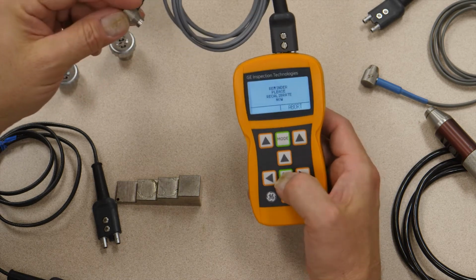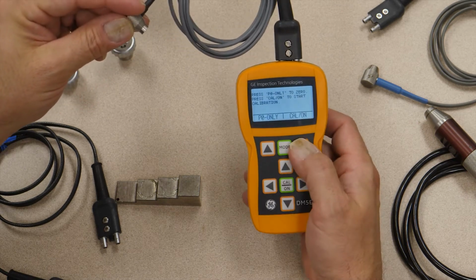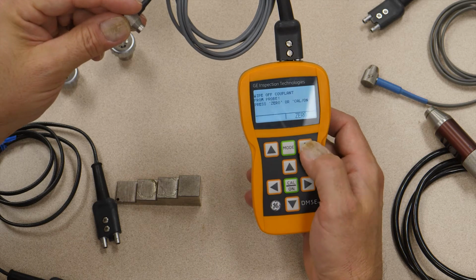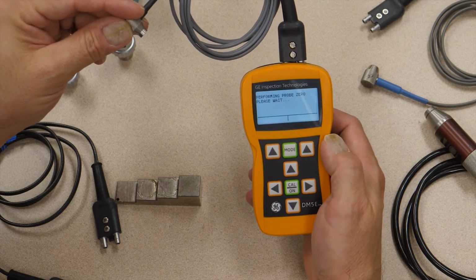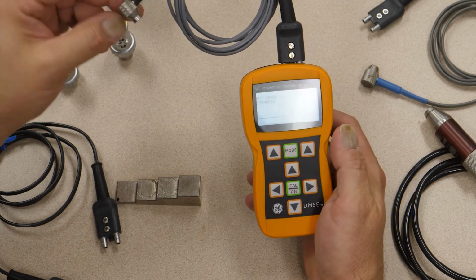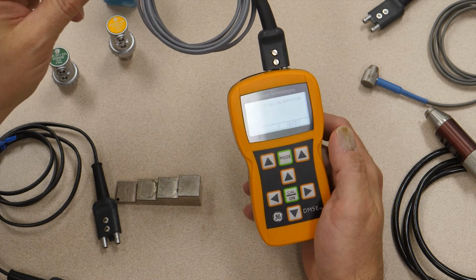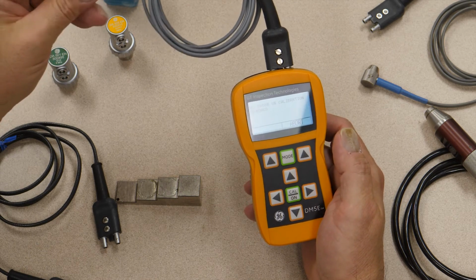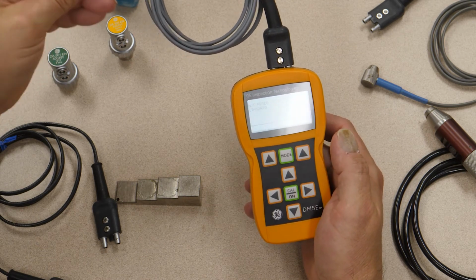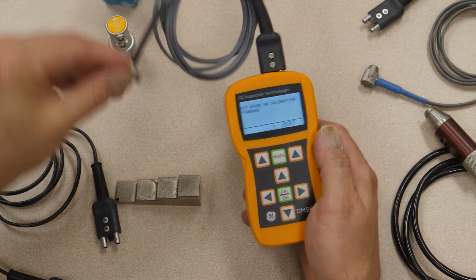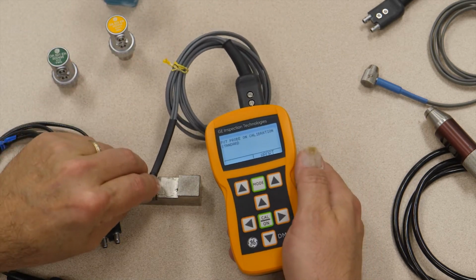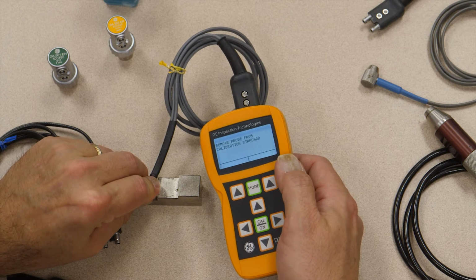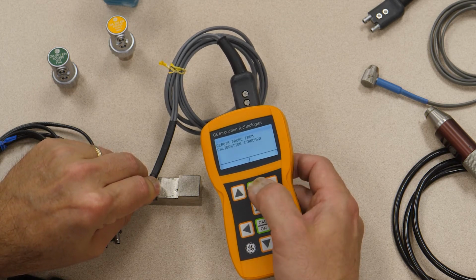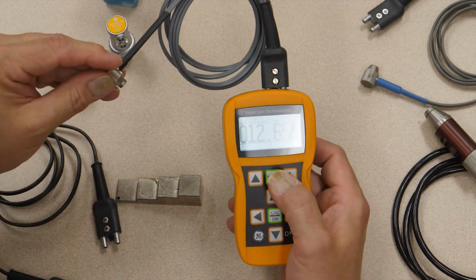We need to run through a calibration. So I say calibrate. I'm going to do a full calibration. I zero the probe. And the DM5E typically uses auto zero, so it's pulsing and listening on each side of the probe right now as the probe's held in the air. Zeros the probe. Now it tells me to couple the probe to the cal block, put it on my 1/2 inch step of my cal block, remove it.